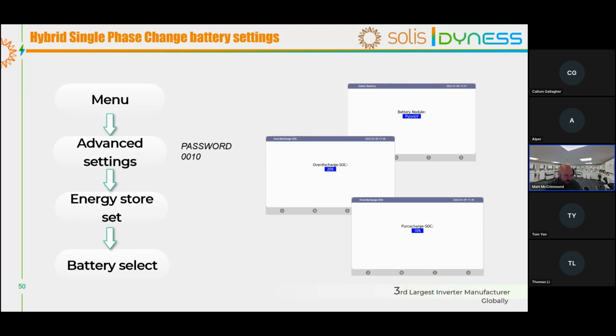So what you need to do is go into advanced settings. When you go to advanced settings, it'll ask you to enter a password. So our password to get into the advanced settings is always 0010, or on the screen it'll be down, down, up, enter. And then you can go through our energy store set menu, then battery select. Once you then select the battery, it'll prompt you to set two values.